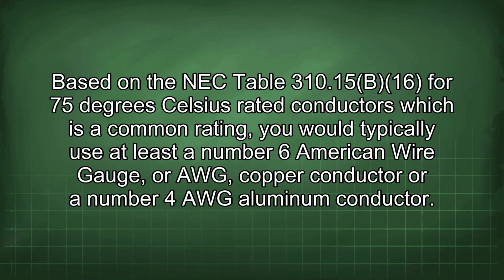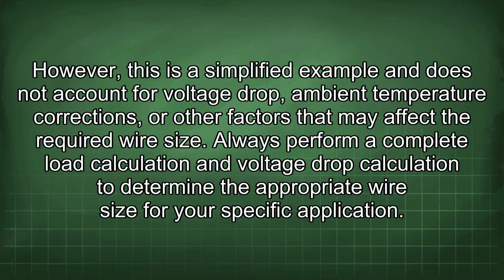Based on the NEC Table 310.15(B)(16) for 75 degrees Celsius rated conductors, which is a common rating, you would typically use at least a number 6 American Wire Gauge, or AWG, copper conductor or a number 4 AWG aluminum conductor. However, this is a simplified example and does not account for voltage drop, ambient temperature corrections, or other factors that may affect the required wire size.